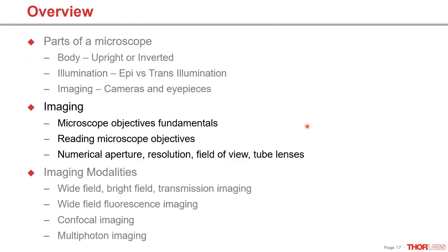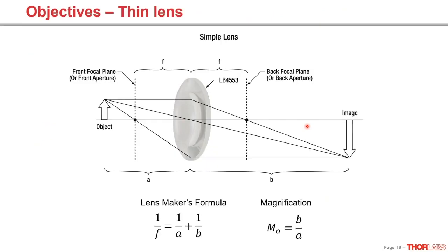Now we'll cover a lot of territory — the core of many questions we get. This includes reading microscope objectives and understanding what all those numbers mean, as well as key concepts such as numerical aperture, resolution, field of view, and tube lenses. A long time ago, simple microscopes were essentially a magnifying glass — a single bi-convex lens with curvature on both sides, with a defined focal length in front and behind. Using the lens maker's formula, 1/F = 1/A + 1/B, we can calculate where an object at distance A is relayed to at distance B. Magnification is simply B/A.